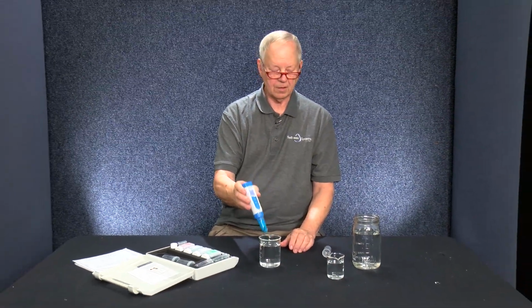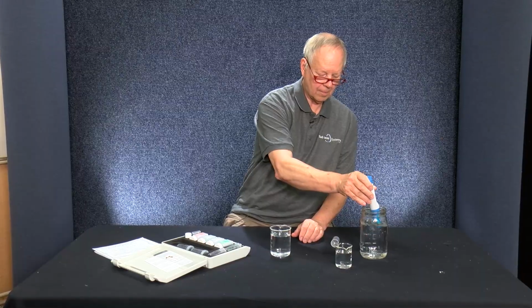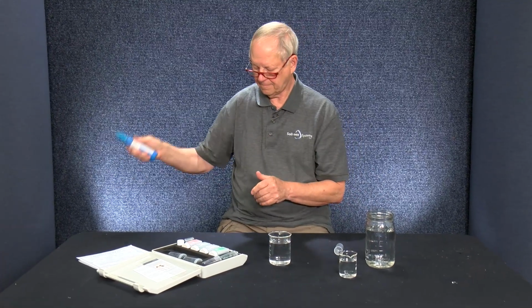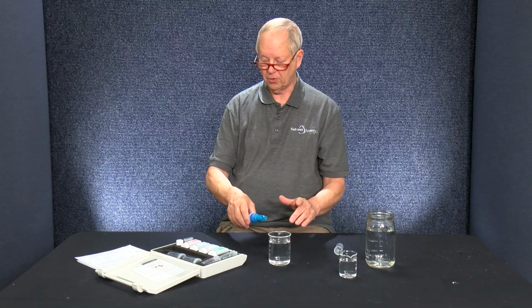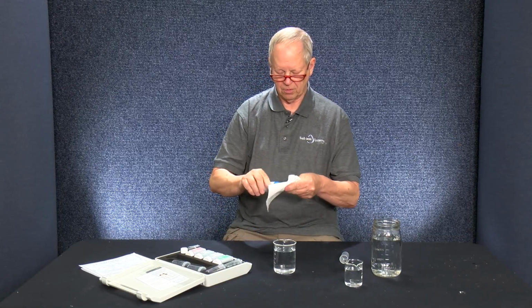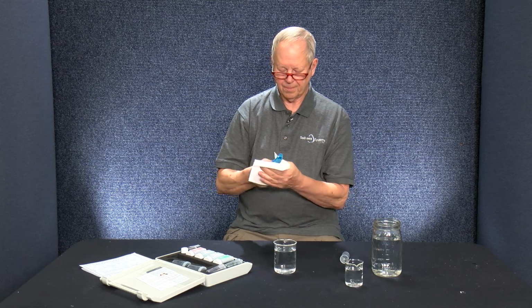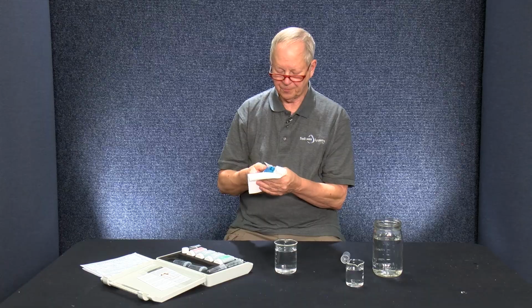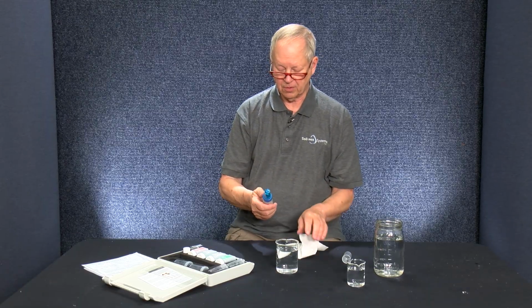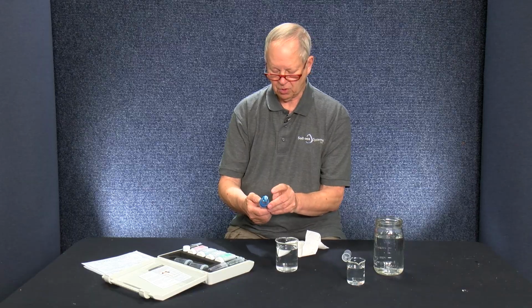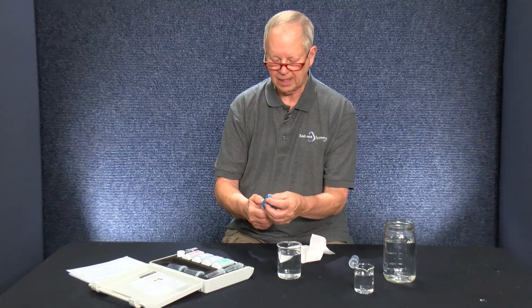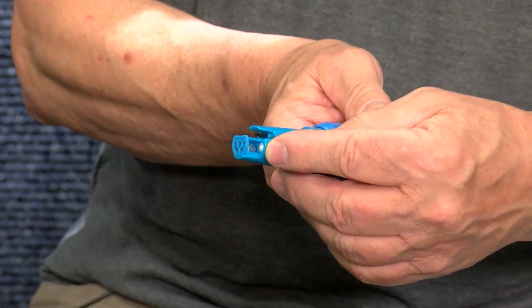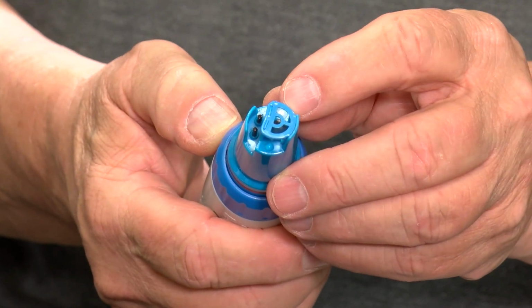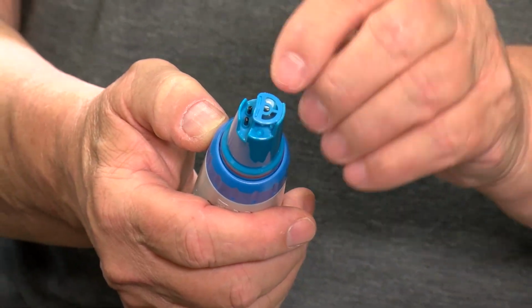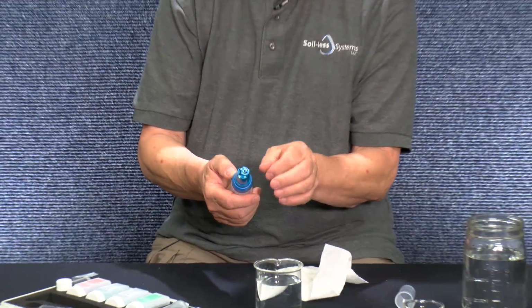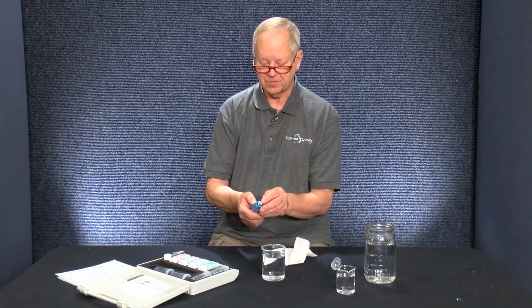Okay, now that we're done with that, again, we rinse it off. Give it a shake. Okay, we need to dry it off. Paper towel, and you wipe off the whole thing. You can blow into it like that. One thing that's kind of interesting on this particular one, and it's going with the new style of apparatus, is they put this little shield on the end to protect the pH bulb that's inside of it. Sometimes it's a little hard to clean, but this will snap right off, so it'll let you clean in there with a Q-tip or some very delicate tool. Don't poke on it too much. These are very expensive to replace.